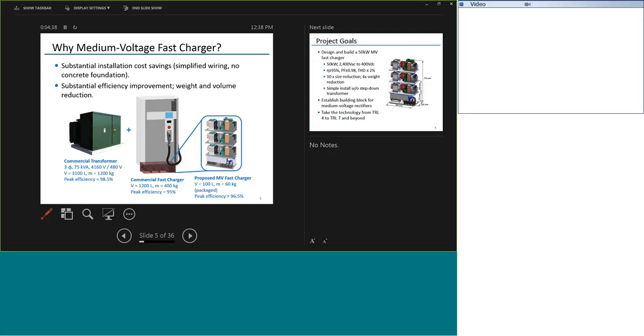What we're proposing is to replace these two components with a single wide bandgap medium voltage fast charger that connects directly to the medium voltage line, with a volume goal of 100 liters and a mass of 60 kilograms. Peak efficiency should exceed 95%, and our goal is 96.5% or higher. Again, the idea is to have a system of similar cost, but to save substantially in terms of operating costs, since the efficiency is higher, and also to save substantially in terms of the installation costs, especially in seismically active areas where concrete pad pours have to be seismically constrained.